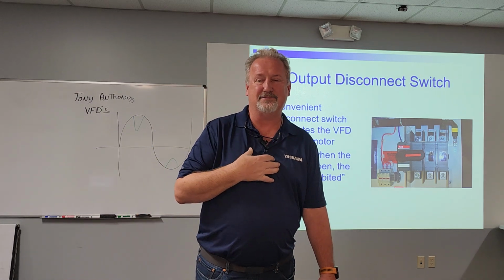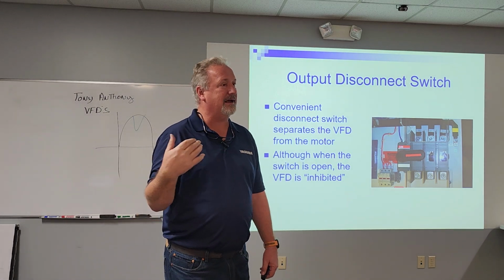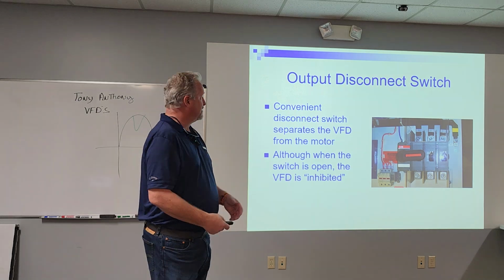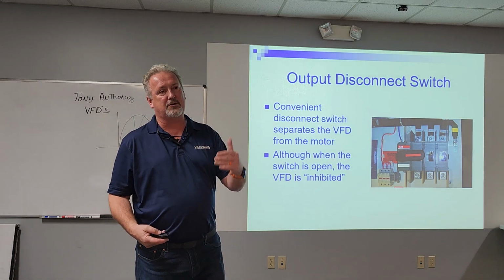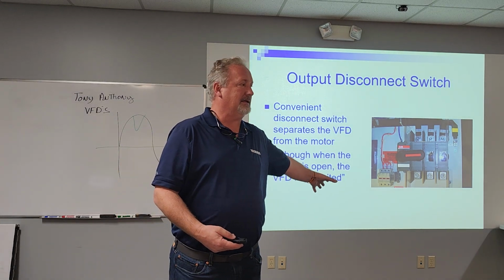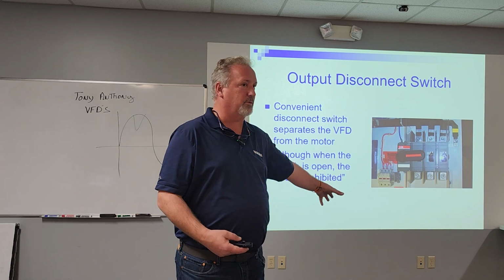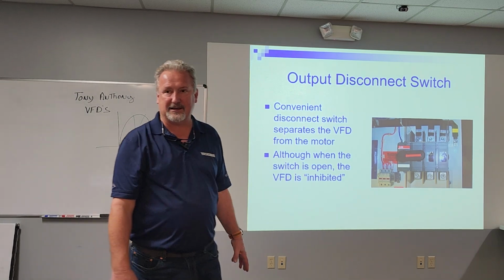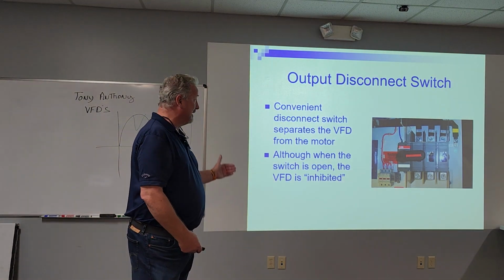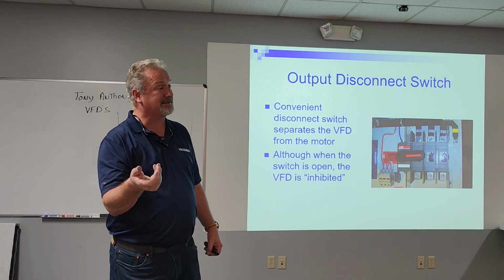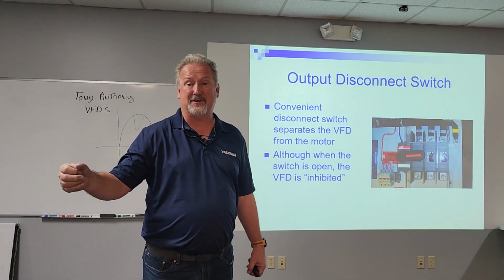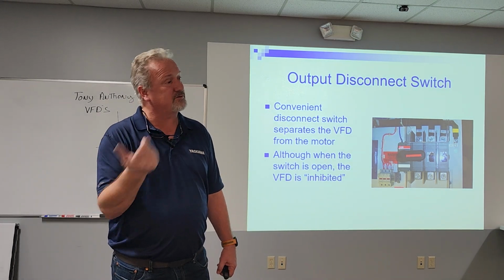Drives don't like that. You're probably going to let the smoke out of the drive and get a new drive. So at a minimum, make sure your lockout tagout says tag out the drive if you're working on that motor and opening that line of sight disconnect. What we really would like to have is some auxiliary contacts, so that if somebody opens that disconnect without tagging out while the drive's still running, it'll trip the drive off.